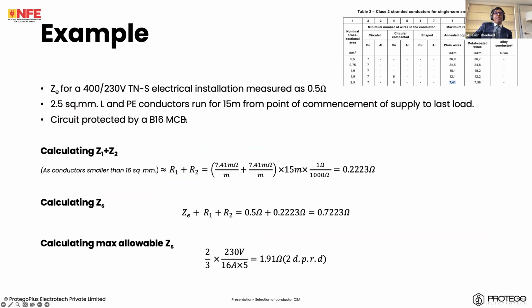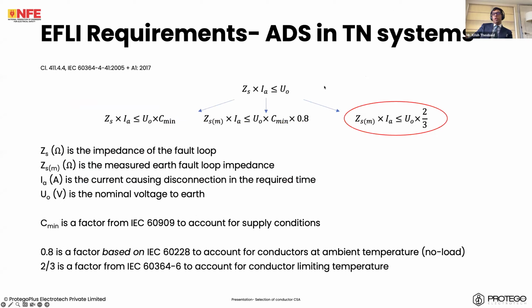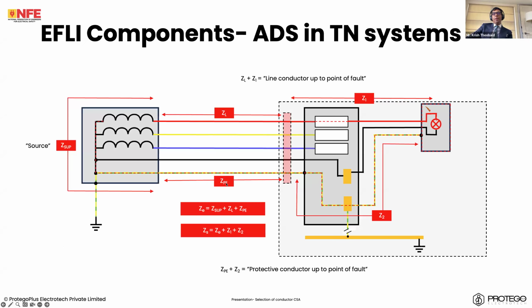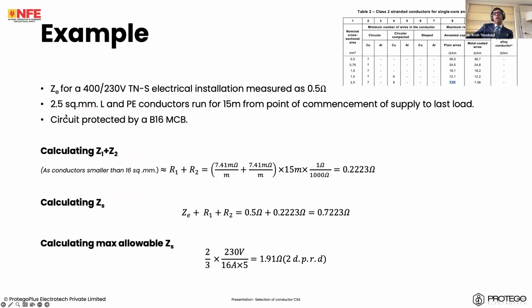So we'll consider a very simple example, conductor smaller than 16 square mm. Consider a 400/230 volt TN-S system. 0.5 ohms is the value of ZL plus ZP plus Z sub e, the measured value of earth fault loop impedance at the point of commencement of supply. I have 2.5 square mm line and PE conductors. These are running for 15 meters from the point of commencement of supply to the last load. Circuit protected by a B16 MCB.